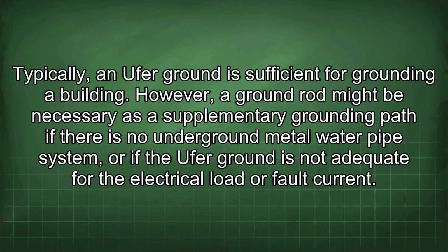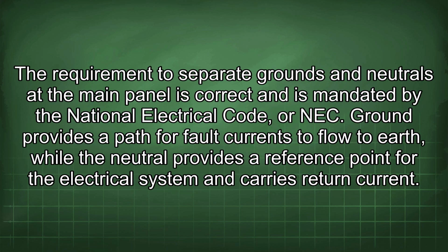However, a ground rod might be necessary as a supplementary grounding path if there is no underground metal water pipe system, or if the Ufer ground is not adequate for the electrical load or fault current. The requirement to separate grounds and neutrals at the main panel is correct and is mandated by the National Electrical Code, or NEC. Ground provides a path for fault currents to flow to earth, while the neutral provides a reference point for the electrical system and carries return current.